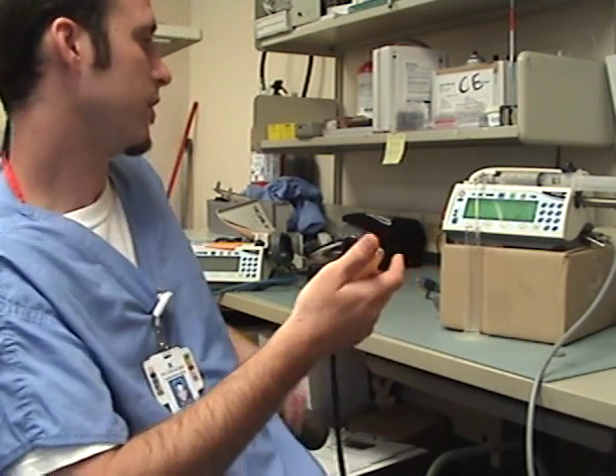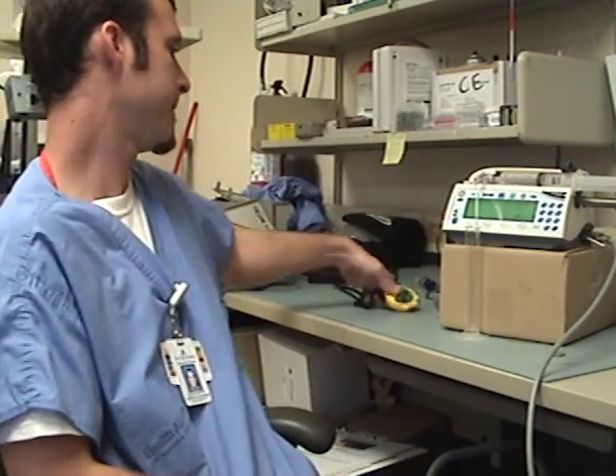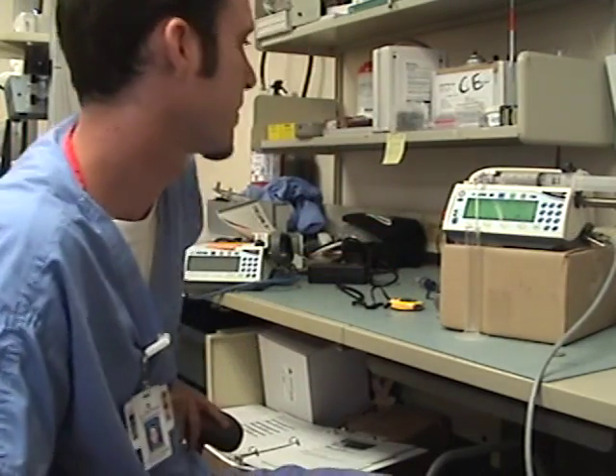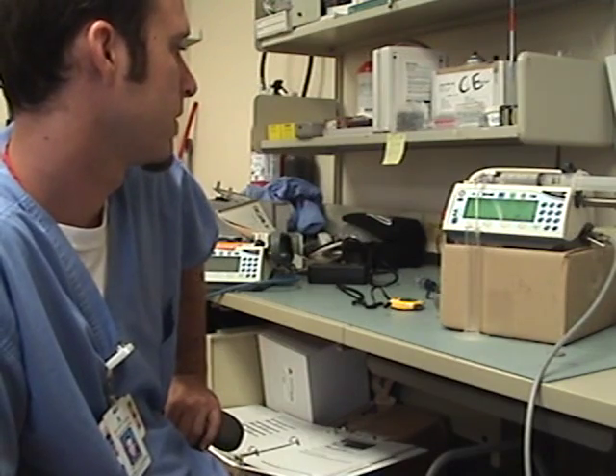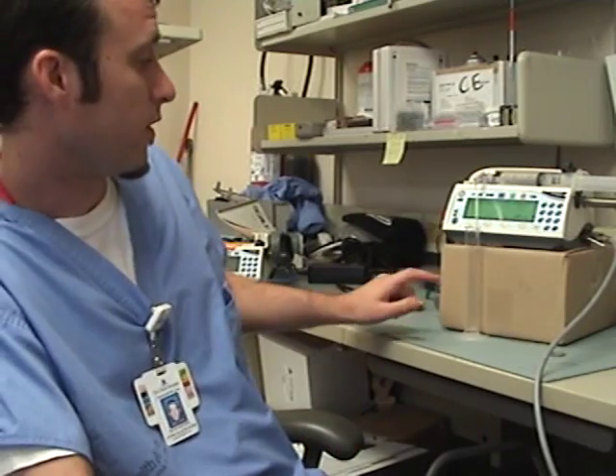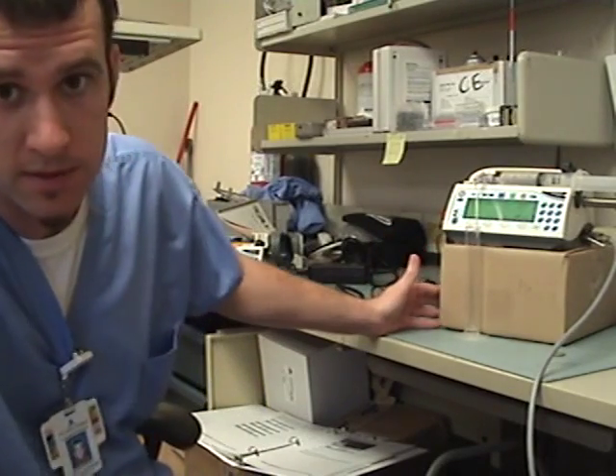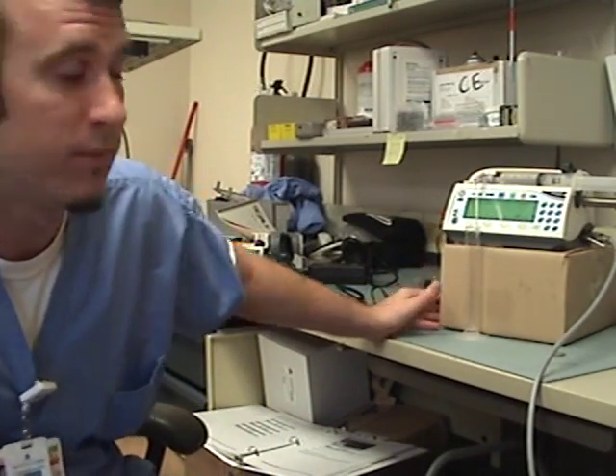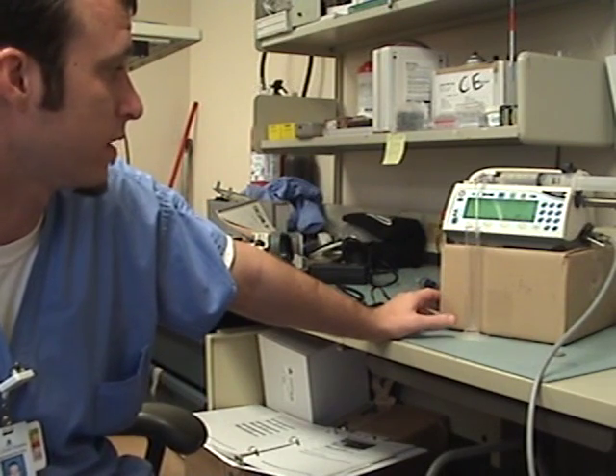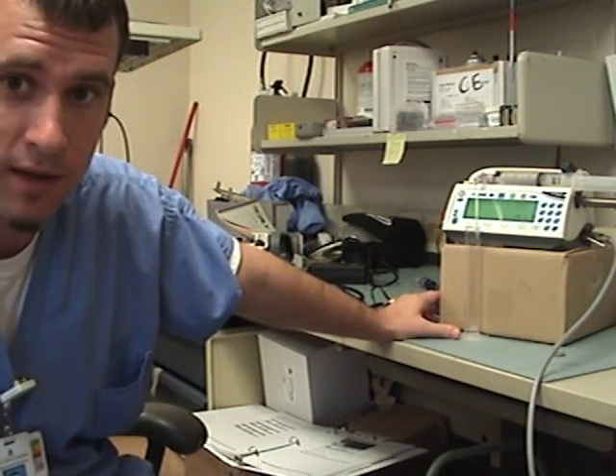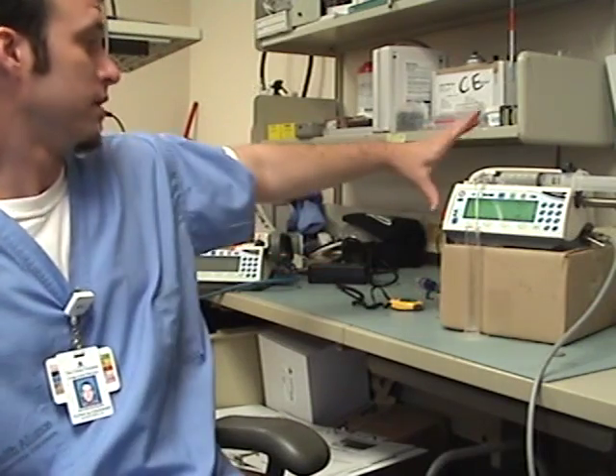Now we just delivered 1 milliliter in 30 seconds. In order to save time at the end of this, we're not going to go ahead and let it run all the way out, but that is the basic step-by-step procedure for doing preventative maintenance on a Medfusion 3500. Once you've verified the accuracy of the delivery rate, change your PM sticker, do your paperwork, and you're done.